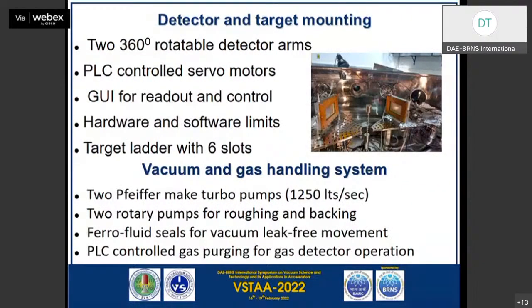And this is the inside view of the chamber, where we have the two detector arms with elevated platforms. You can see there are radial holes. In the bigger one, we have 9 holes, 10 degrees apart. So it covers 80 degrees, and the smaller arm has 40 degree coverage with 5 radial holes, where we can put our detectors at different angles and distances.